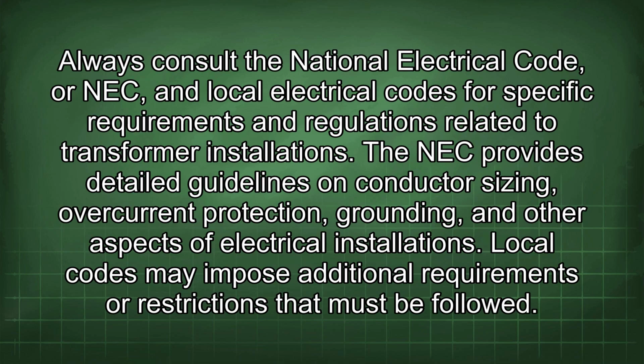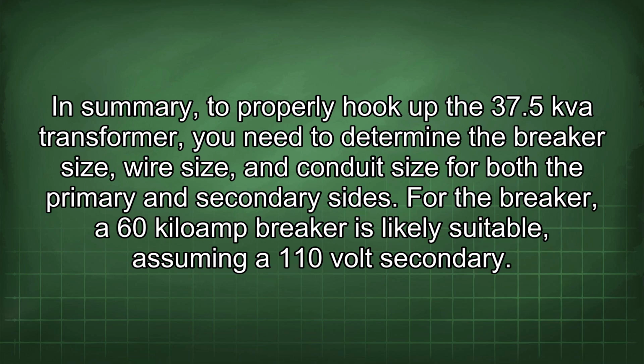Always consult the National Electrical Code (NEC) and local electrical codes for specific requirements and regulations related to transformer installations. The NEC provides detailed guidelines on conductor sizing, overcurrent protection, grounding, and other aspects of electrical installations. Local codes may impose additional requirements or restrictions that must be followed. In summary, to properly hook up the 37.5 kVA transformer, you need to determine the breaker size, wire size, and conduit size for both the primary and secondary sides.